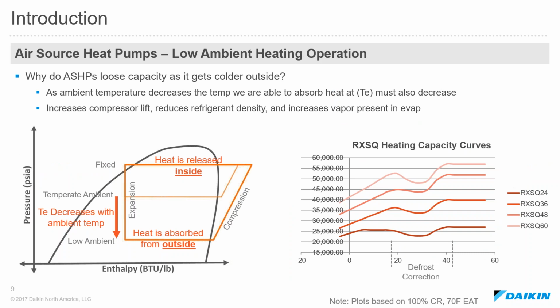Now, before we discuss that solution, I just want to provide a little more information for those of you who are interested in why we lose capacity as it gets colder outside. I promise this is the only time you'll see a pressure enthalpy chart throughout the presentation. So in the bottom left corner, that's a pressure enthalpy chart, and just in the simplest sense, a pressure enthalpy chart has a horizontal line on the top. That's the high side pressure of the system, or the temperature that we're releasing heat inside.